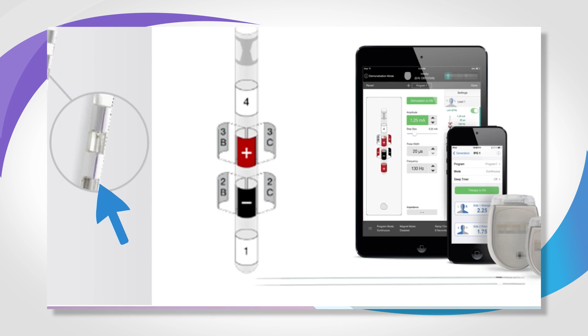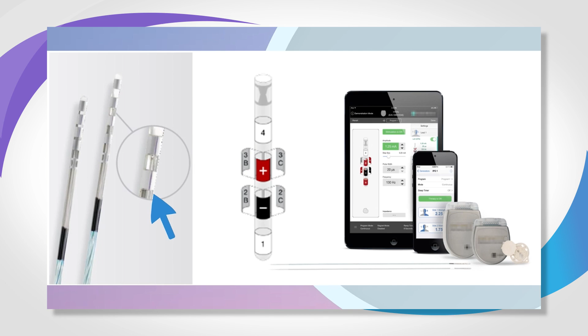The Abbott device here on the left, you can see the segmented electrodes, narrow and wide spaced. This is a graphic representation, and again the numbering is 2 ABC, 3 ABC, and 4. With negative contact 2A and positive 3B, that is a bipolar configuration. This device is Bluetooth enabled, uses Apple devices, so we have to pair our device to the patient's battery in their chest. This device allows us to do remote programming, so we can work through a patient's Wi-Fi and change settings in real time. This device is also MRI conditional and non-rechargeable at the moment.